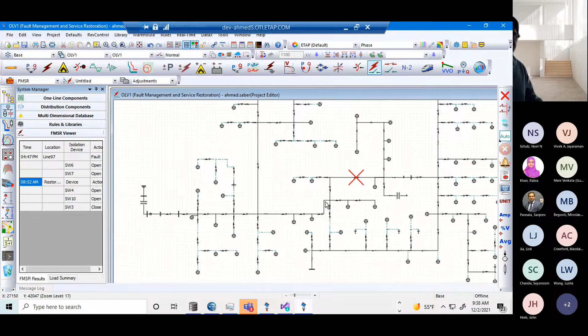The initial loss, without any change, was 96.18. But after running Volt-VAR optimization, I can see 85.89. Why? Because the initial minimum voltage was 98.81%, but the final minimum voltage is 95%. That is accepted, right? 95% is actually the standard in USA. Then we can go until 90%.